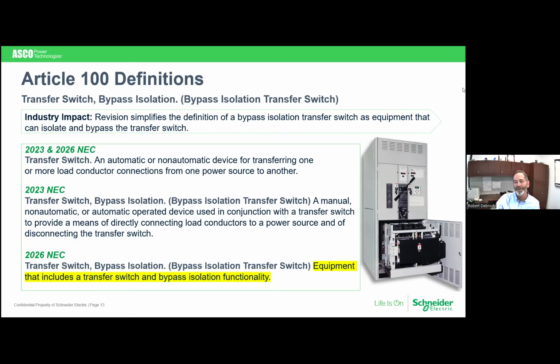So if you look at the picture off to the right, this is a bypass isolation transfer switch. And really, it's just two transfer switches in the same enclosure, and they're working in parallel with each other. Or sorry, one is the backup to the other, so that if anything happened to that transfer switch, you can always bypass it. It's already connected up to both sources and the loads, so it's easy to bypass it and go from one to the other. And then once you bypass it, you have the ability to test that transfer switch, and you have the ability to isolate it, as shown in this picture here, where you can actually pull out the complete transfer switch. You can perform maintenance on it. You can actually replace the whole transfer switch if you wanted to.